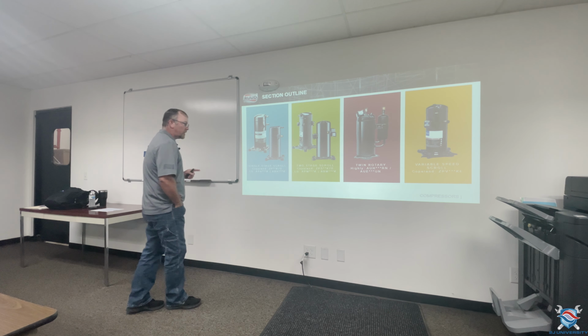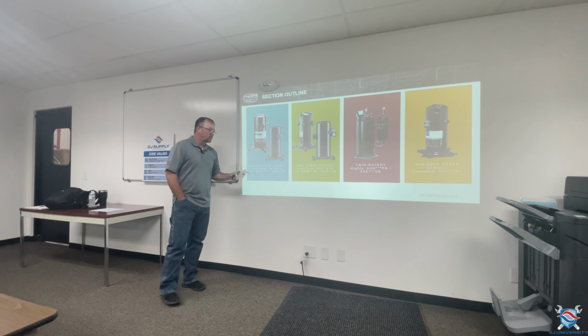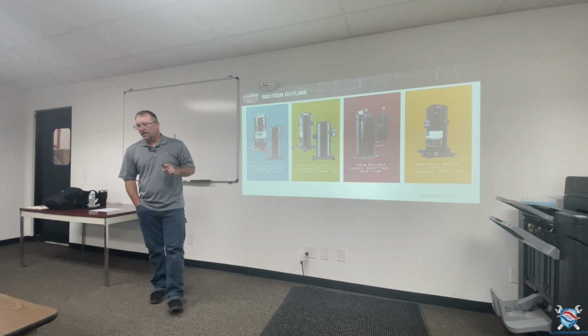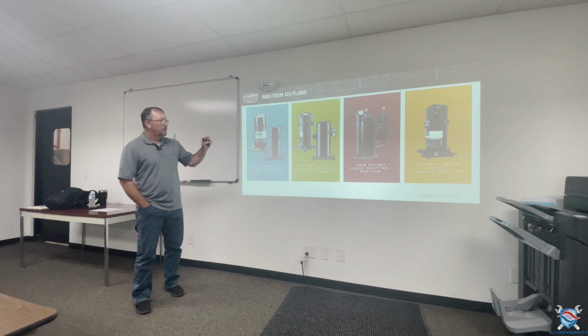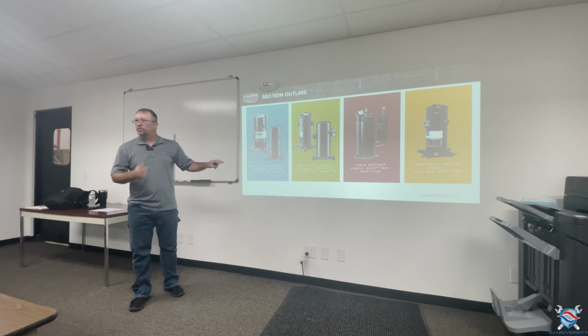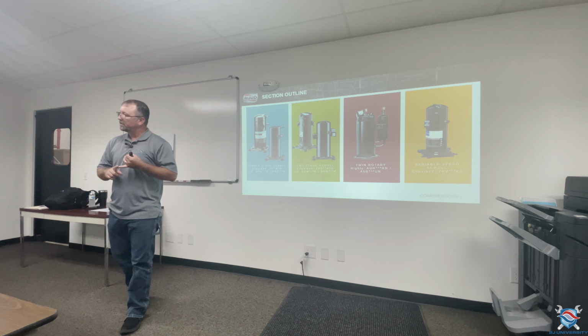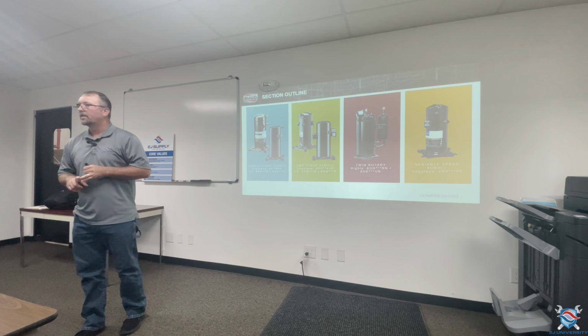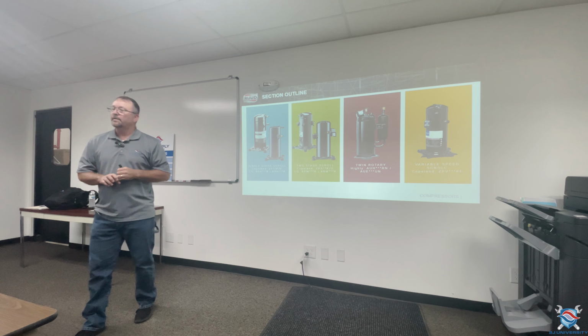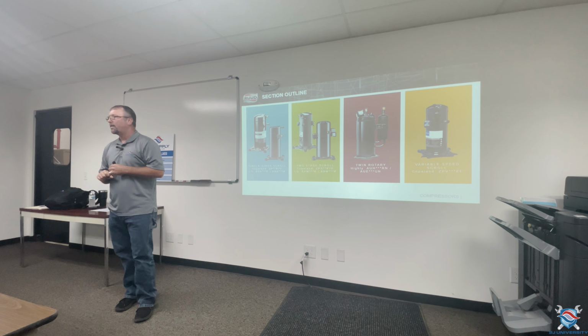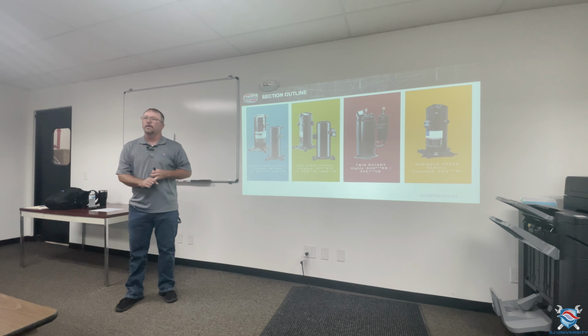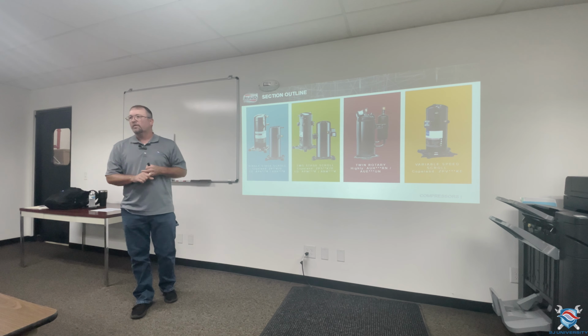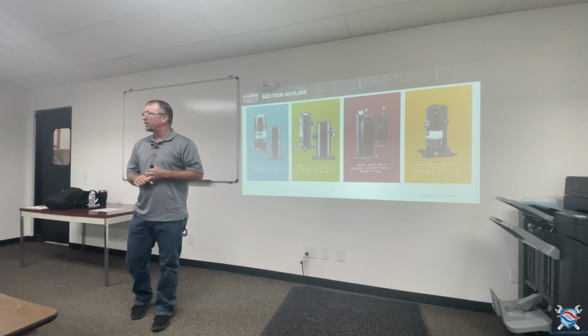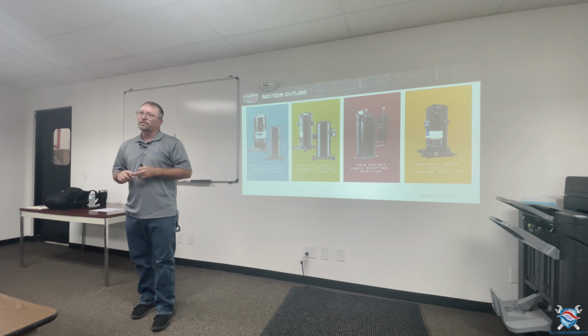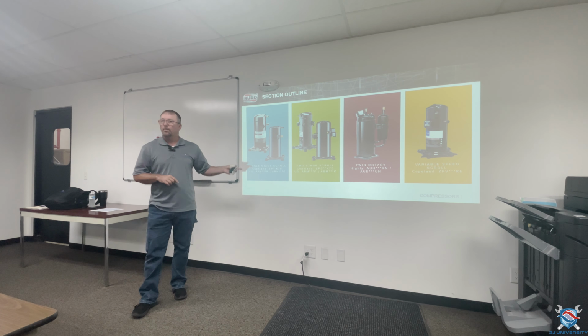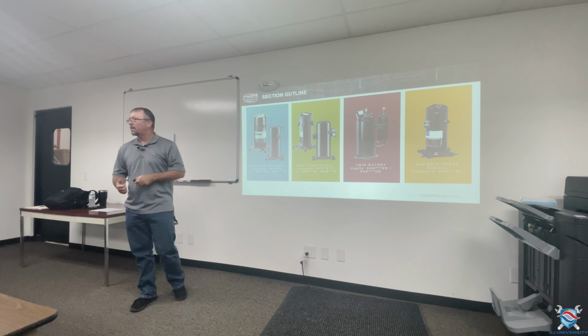Your 2-stage scrolls and single-stage scrolls, the reason I have this up here is because right now they're using 2 different scrolls. They're using an LG scroll and a Copeland scroll. So when you call in, it is adamant that you have model and serial number off that unit, because every unit that comes out will have a compressor code, and it's going to tell us whether there was an LG scroll or a Copeland scroll in there so we can get you the right replacement.